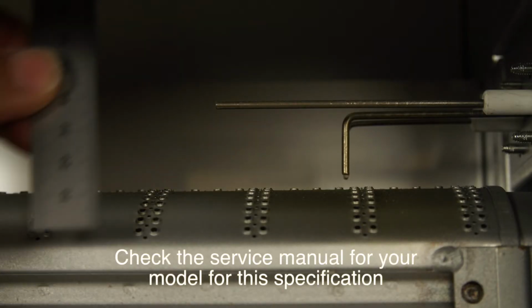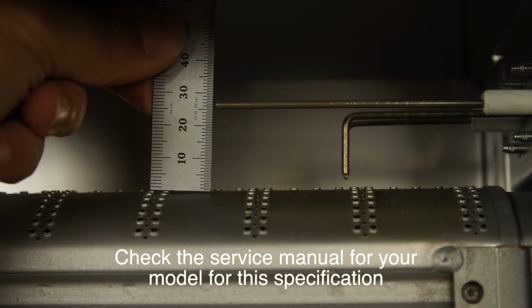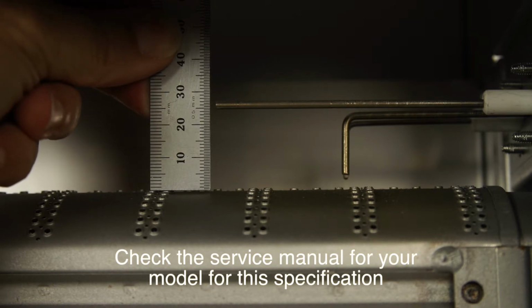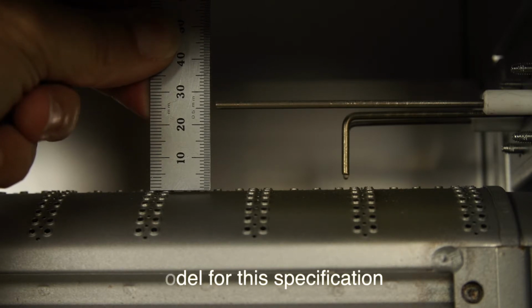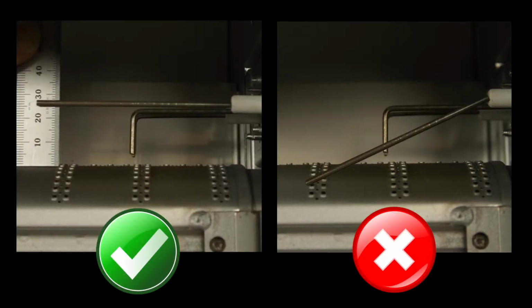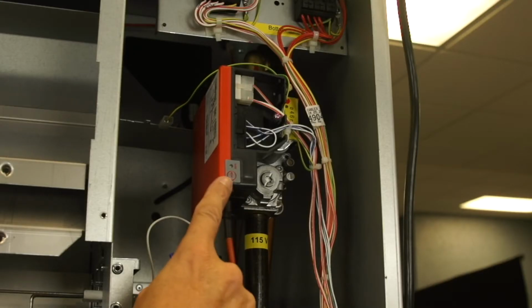Also, check that the flame sensor is properly positioned above the burner tube. Too much distance between the sensor rod and the burner, or contact between the flame sensor rod and the burner tube, will also result in an ignition failure. If the above items are checked and found to be in order, but the error persists, we recommend that you replace the ignition control module.